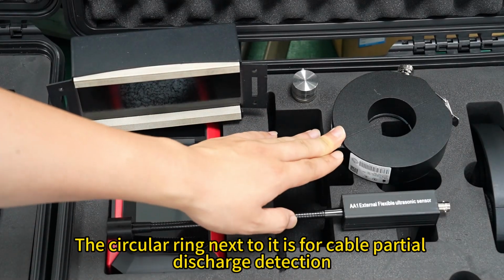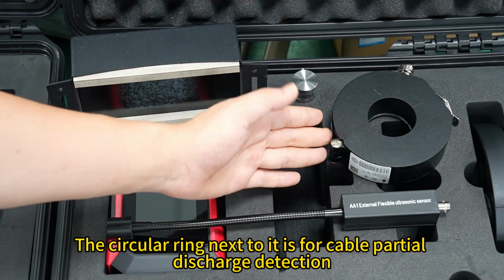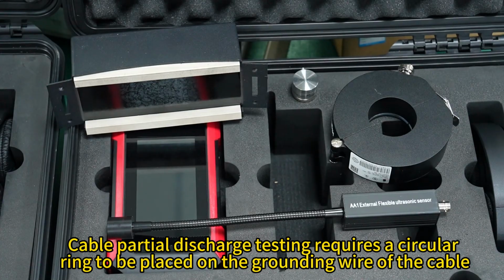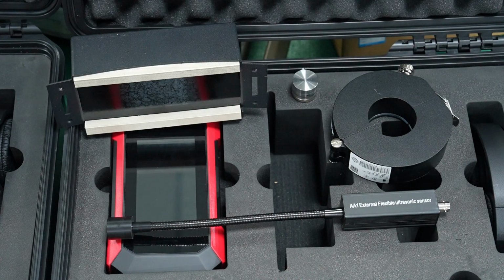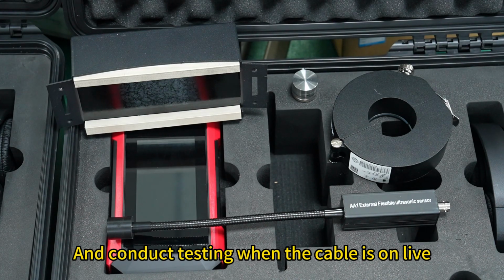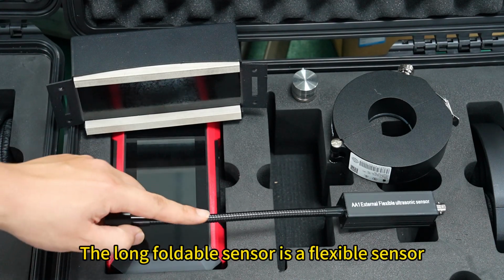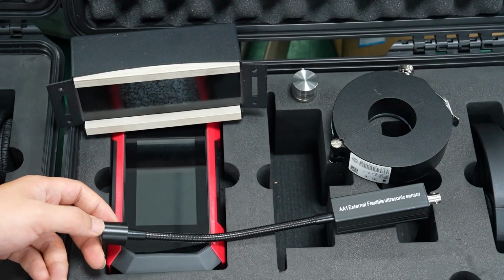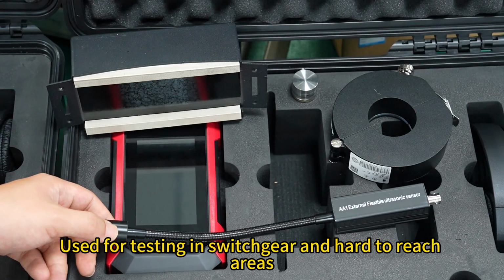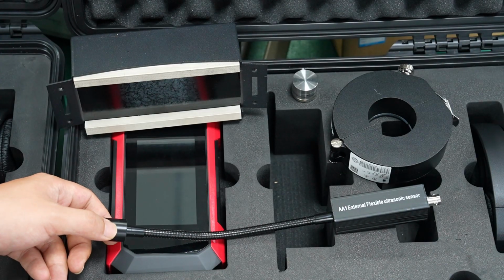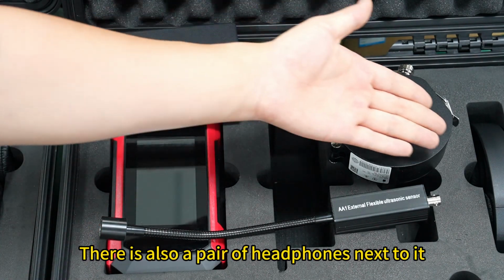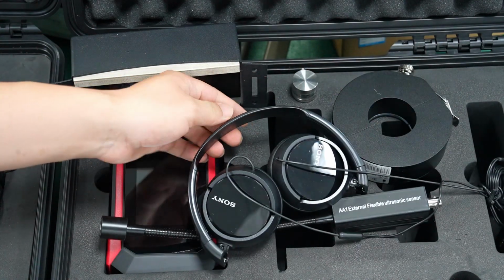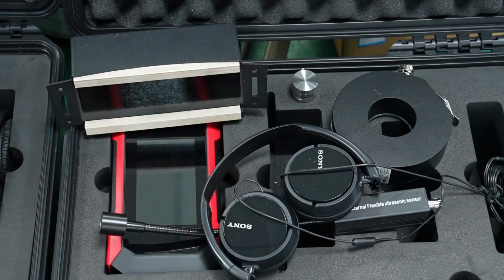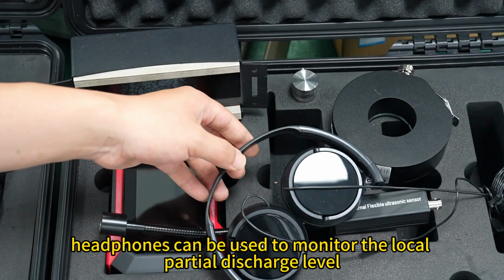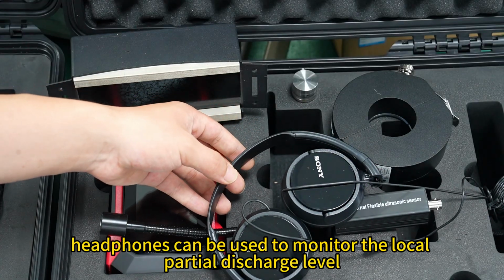The circular ring next to it is for cable partial discharge detection. Cable partial discharge testing requires the circular ring to be placed on the grounding wire of the cable, and testing is conducted while the cable is live. The long foldable sensor is a flexible sensor, used for testing in switchgear and hard-to-reach areas. There is also a pair of headphones next to it. During testing, headphones can be used to monitor the local partial discharge level.